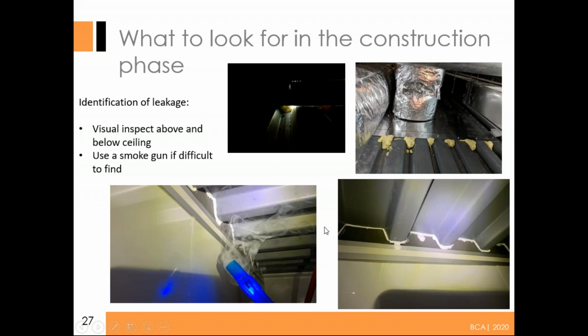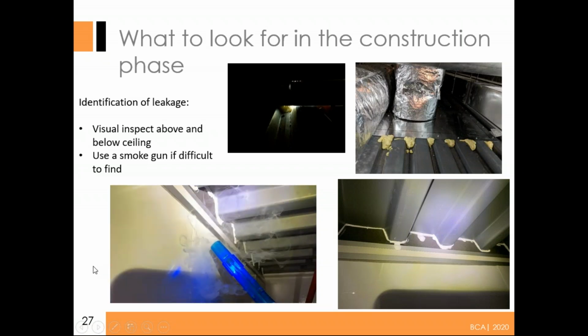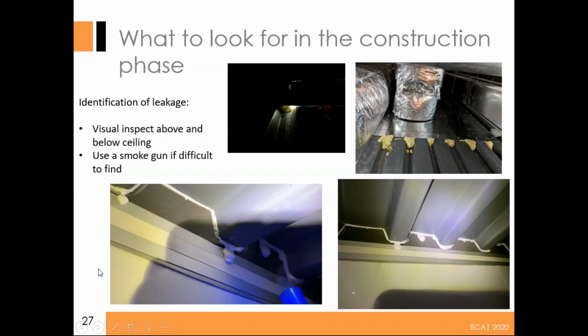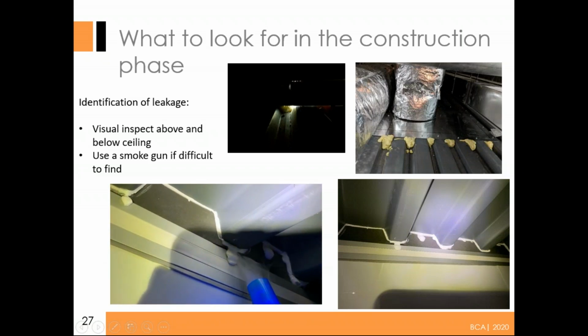Here's another example. I might not go too deep into it, but we just talked about sealing. This is one where we had a corrugated ceiling, corrugated decking for the ceiling. A lot of times you're going to talk about making sure that the corrugation is sealed up. That's somewhat easy to do, but the difficult part is that every penetration through that corrugated piece of metal has to have this wonky sealing. Sometimes you have leaks and you've got to go up there in the dark and look for sunlight coming through. If you need help finding it, you can use smoke tests. Here's a video of no leak, and here's a video of a leak. You can see it being sucked right in there.